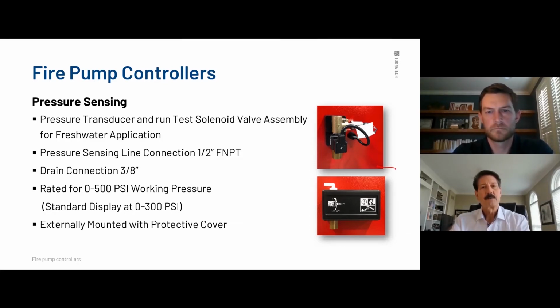The block itself is rated for 0 to 500 PSI. Standard display set for 0 to 300. That's pretty much more than sufficient. If you get into high pressure situations, let us know. We can do factory adjustments with an option for higher. We could actually do it in the field if necessary. And what's nice about this is that it's all externally mounted. We have a high impact polycarbonate cover, as you can see in the picture right here.